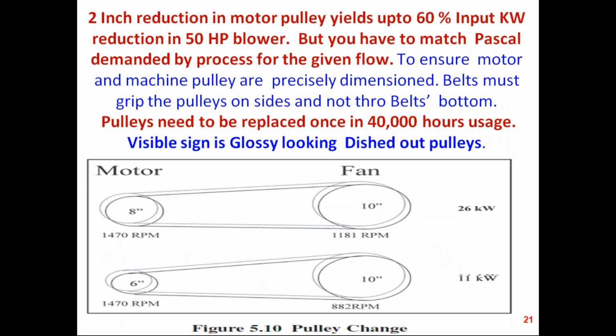A simple operation here for a given industry, this is there in our Bureau of Energy Efficiency bulletins and in our refresher guide also. This 2-inch reduction in the motor pulley gave almost 60% input kilowatt reduction. From an 8-inch motor pulley, this industry reduced to 6-inch. Automatically, it's a 50 HP motor. From 26 kilowatt, it came down to almost 11 kilowatt. This is on a centrifugal fan application.